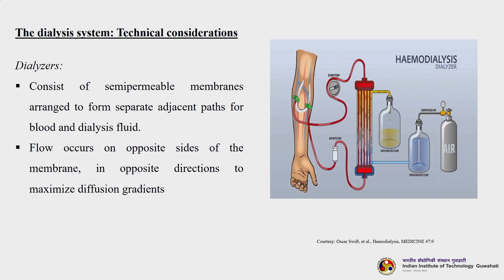The dialyser consists of a semi-permeable membrane arranged to form separate adjacent paths for blood and dialysis fluid. Flow occurs on opposite sides of the membrane in opposite directions to maximize diffusional gradients. Blood is pumped in, flows through, and dialysate (buffer solution or water) passes on the other side in the opposite direction. The separation occurs, the effluent enriched with salts is collected, and the purified, volume-reduced blood with toxic components removed is fed back to the patient.